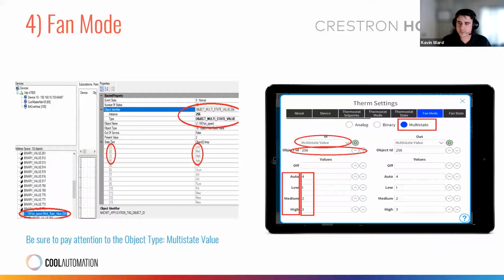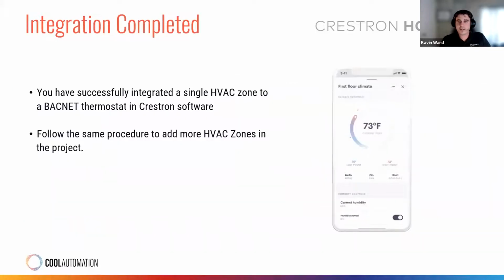Once you're done with those four tabs, your integration is complete. You've mapped everything out and have a clean user interface in Crestron Home. With multiple indoor units, you'll repeat the process by continuing to scroll down on your object IDs. You'll find L1 101, or whatever address has been identified, and use those same points to complete the mapping for your next BACnet thermostat for the 2nd zone, 3rd zone, etc. It really is a copy-paste solution once you've discovered it in Yabe and have everything open.